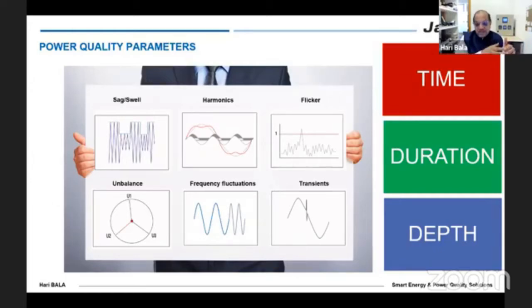And depth is the magnitude of what is happening. Say if it is an under voltage, how low the voltage is going or how high the voltage is going. If it is harmonics, again, how high or low the harmonics are, and what is the duration of this particular harmonics. If it is continuous, or if it is for a short time, or for a longer time, all those things have to be calculated. So it's very important in power quality parameters to understand time, duration, and depth. So that's how the whole thing is represented for power quality.